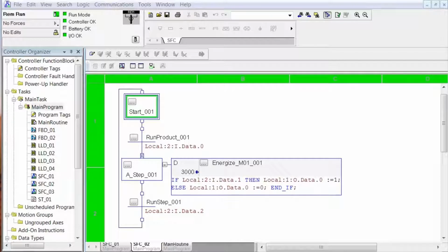So again, even though you time delay, you just delay that action. So if you transition into step 1 for 2 seconds and then transitioned out of step 1 back to the start, that code never got executed, because remember, the timer has a preset of 3 seconds. If I go into step 1 and then go into step 2, see, it never went active because it's time delayed.